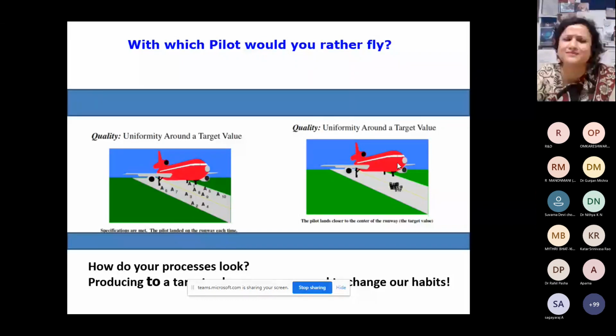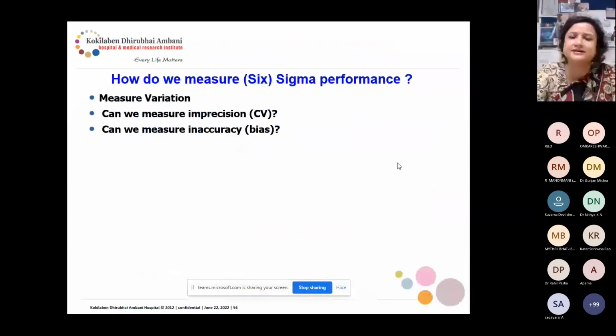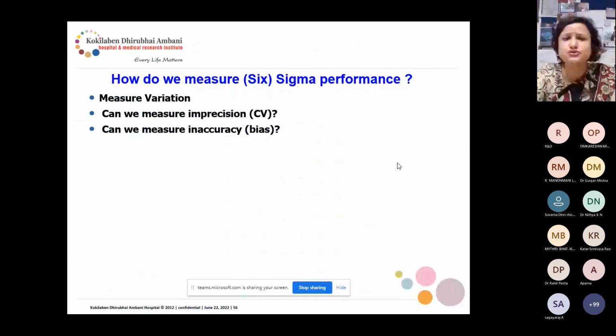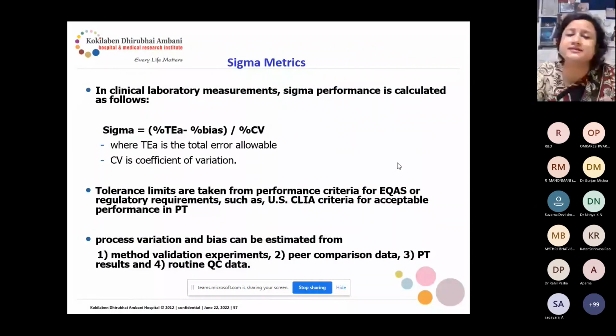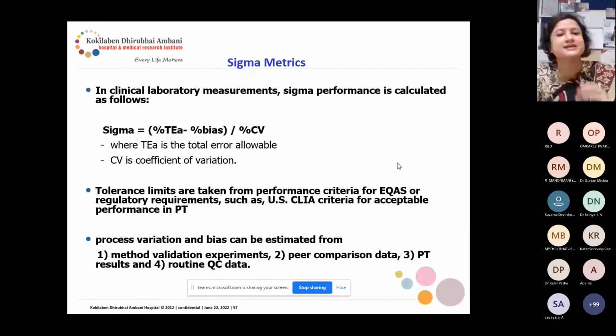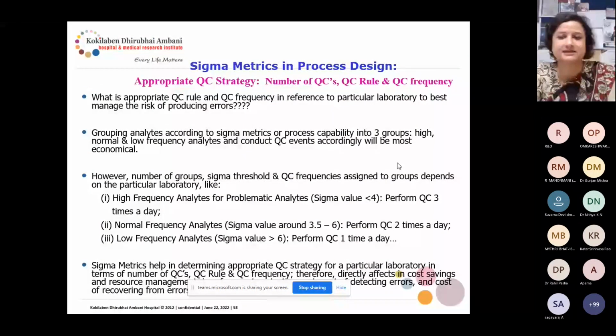So they want not only the specification to be met, they want results near the target value. Because of that, measuring the variation, the CV percentage, and the inaccuracy or bias is very important. And this is the calculation showing how, from total allowable error, bias and CV percentage, we can calculate that. So based on that, what is the rule in our lab?